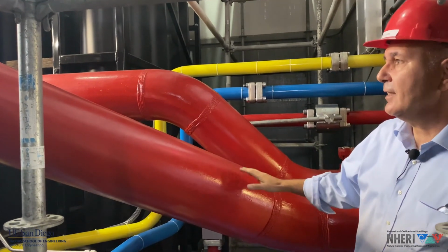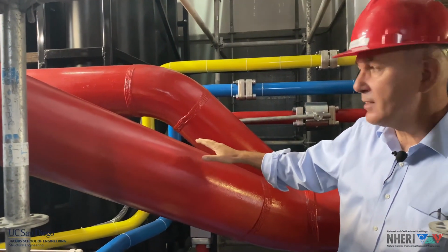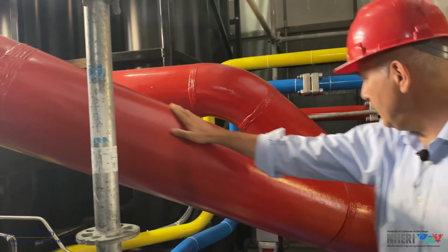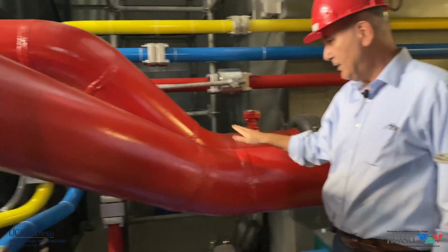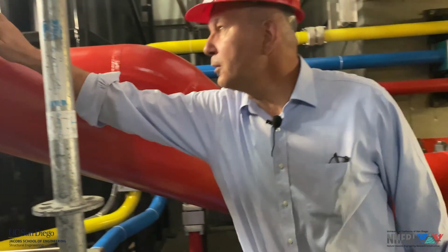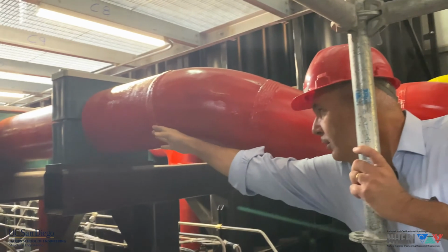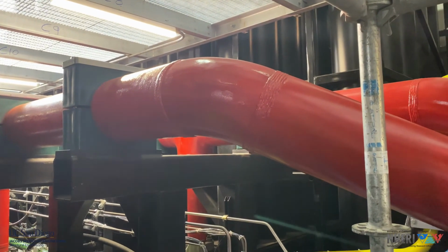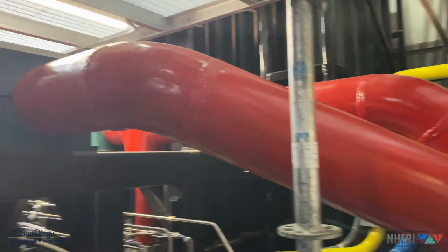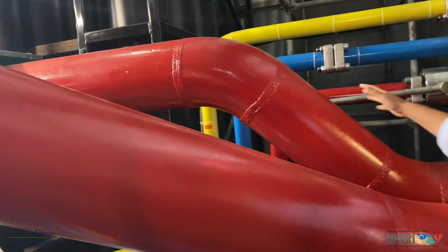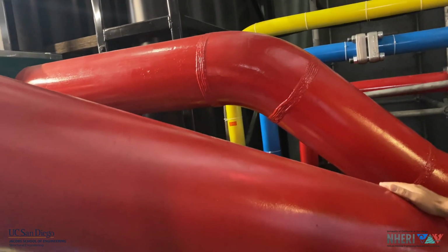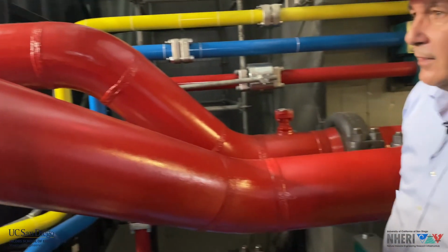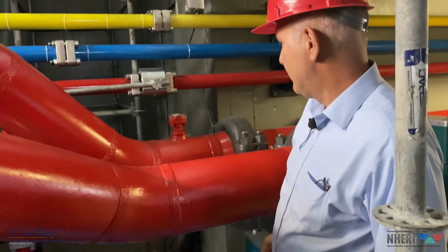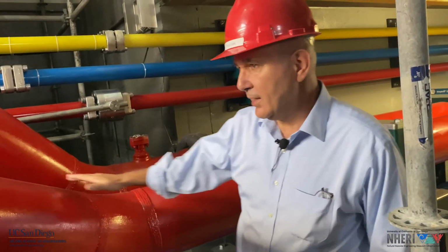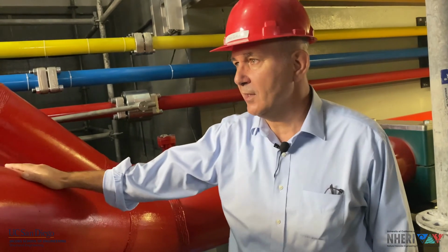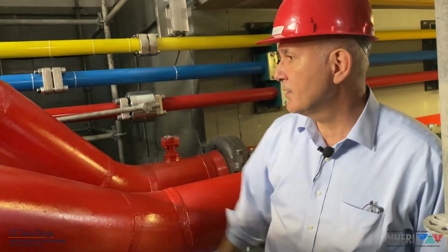Most of these pressure pipes were prefabricated by GS Hydro in Houston. One link had to be welded on site here, the one I'm showing you. You see these 1, 2, 3, and 4 big circular welds. Same thing for the second pipe in the back. These took a long time and had to be x-rayed like all the other welds. These are huge pipes, 12-inch diameter inside, 1 1/4 inch thickness.